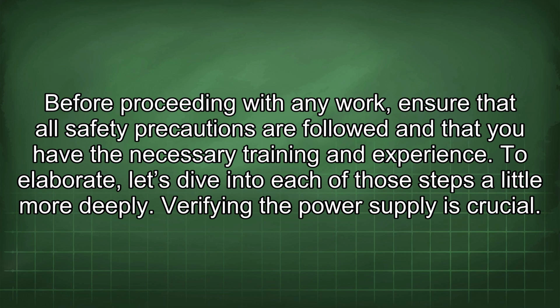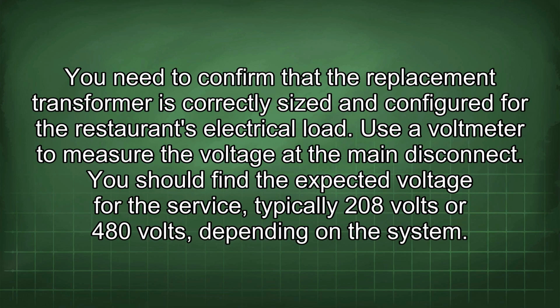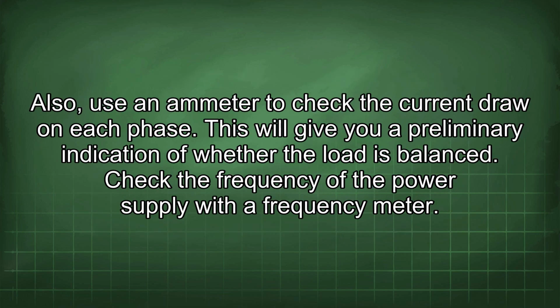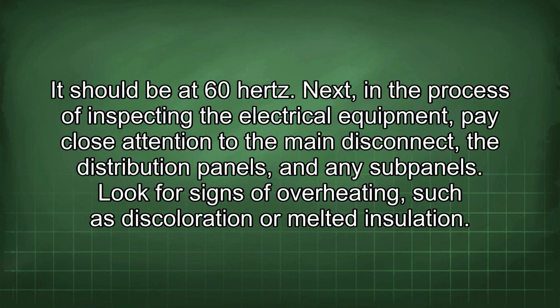Verifying the power supply is crucial. You need to confirm that the replacement transformer is correctly sized and configured for the restaurant's electrical load. Use a voltmeter to measure the voltage at the main disconnect. You should find the expected voltage for the service, typically 208 volts or 480 volts, depending on the system. Also, use an ammeter to check the current draw on each phase. This will give you a preliminary indication of whether the load is balanced. Check the frequency of the power supply with a frequency meter. It should be at 60 Hz.